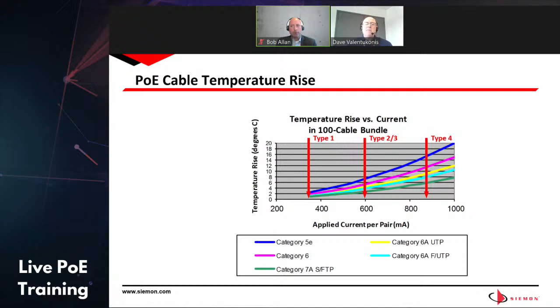And when we say up to 60 degrees, we're assuming an ambient temperature of about 45 degrees C with a heat rise of about 15 degrees C, which gets you up to the 60 degrees C, which is the typical jacket rating of these cables. So if you look at these types of things, you see that along the way here, if you were in an environment like that, you would actually have to reduce your category 6A UTP cabling up to 18 meters at 60 degrees C, which is significant in a 100-meter channel. That's about a 20% derating to address and manage that insertion loss.